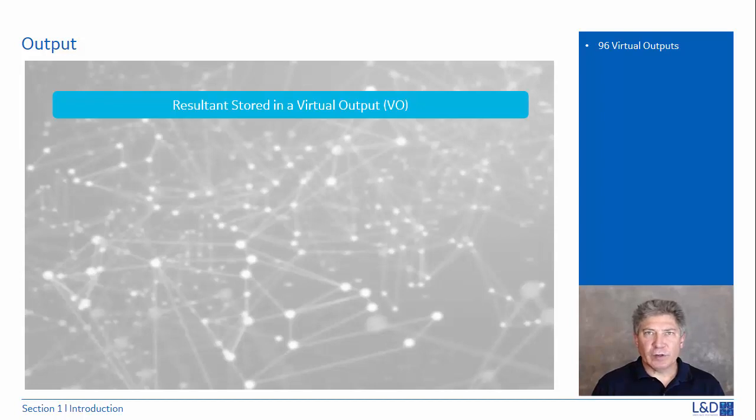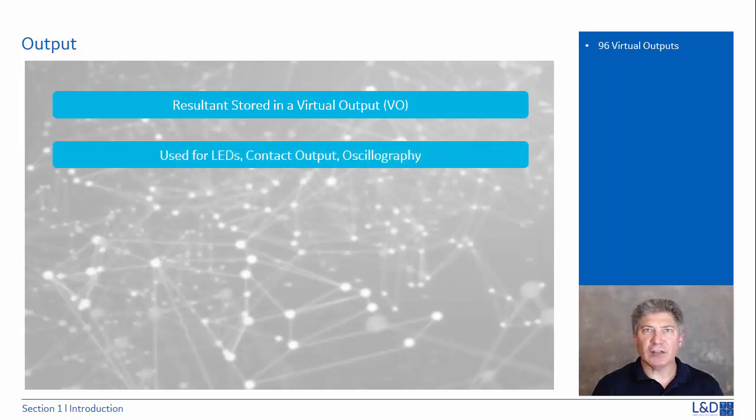Since the UR is signal-driven, the virtual output provides the means to control different functions of the UR, such as controlling LEDs, contact outputs, oscillography, etc. Virtual outputs can also be used as inputs into another equation or logic.